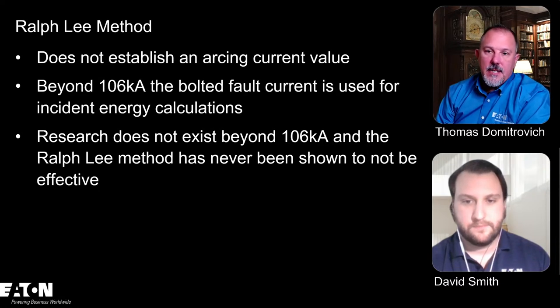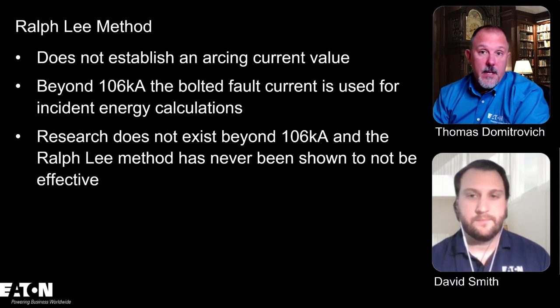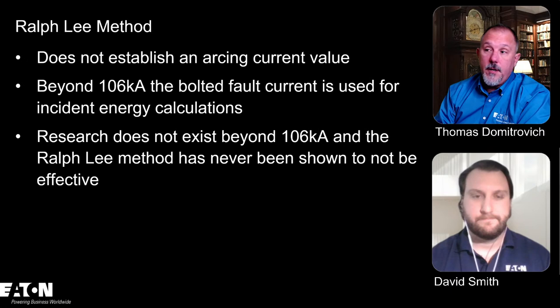But beyond 106,000 amps, that's what we use. And research doesn't exist beyond 106,000 amps. This would be a good, and I've toyed with the idea of doing an IEEE paper on this. Taking some data points, sit in the lab, and we can generate up to 300,000 amps in our Bussmann facility in Ellisville in St. Louis, Missouri.